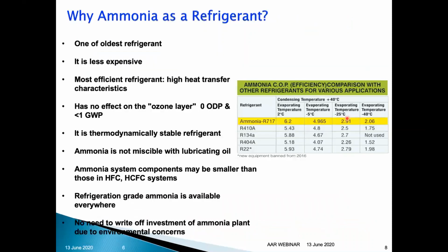So why do we have to have ammonia as a refrigerant? It is one of the oldest refrigerants. It is a byproduct of the fertilizer plant, so the cost is very, very low compared to any other refrigerant. Typically, you can get ammonia at around 1 USD per kg in India, whereas other refrigerants like 404A will cost you around 8 to 10 USD per kg. It is the most highly efficient refrigerant. It has no effect on the environment: 0 ODP and 1 GWP. That is, ozone depletion potential is 0 and global warming potential is less than 1.